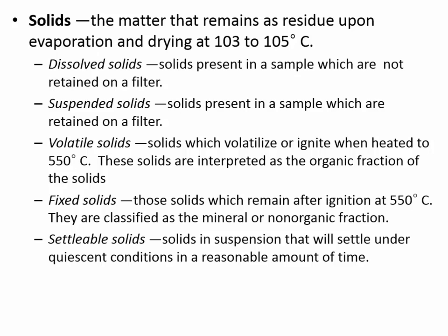Okay, so suspended solids has two subsets. There's volatile and fixed. If you add them together, that is the suspended solids. And dissolved solids is something entirely different. It is the salts that would pass through a filter if you were trying to filter a wastewater. Settleable solids is that fraction of the suspended solids and the volatile solids that are big enough and have a high enough density that over time they'd settle out of the water.